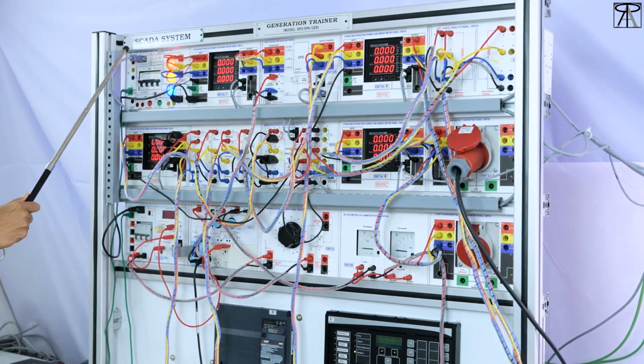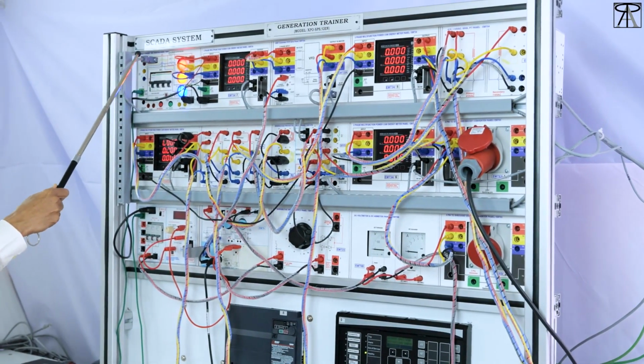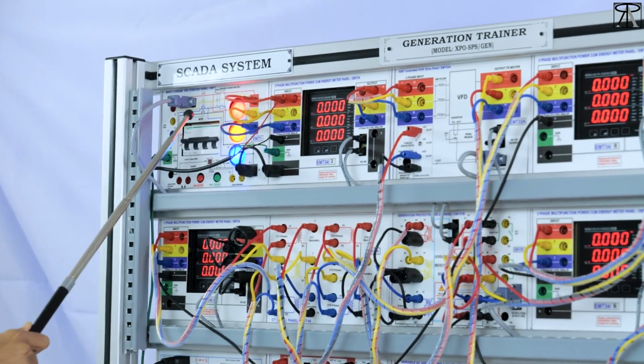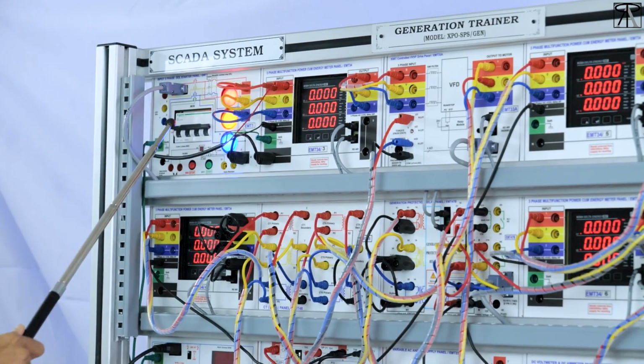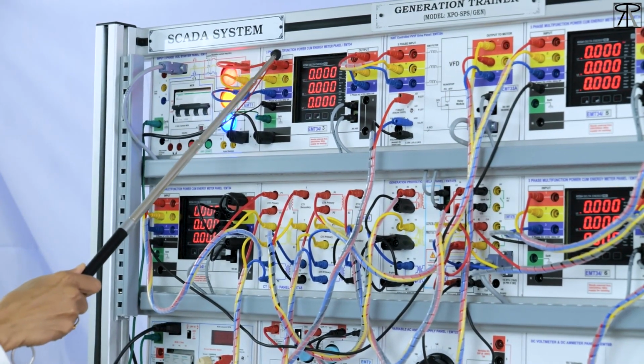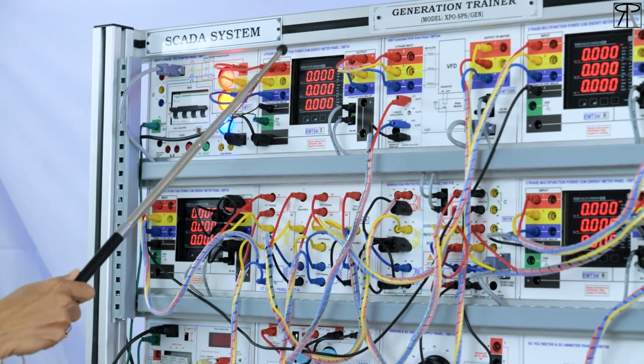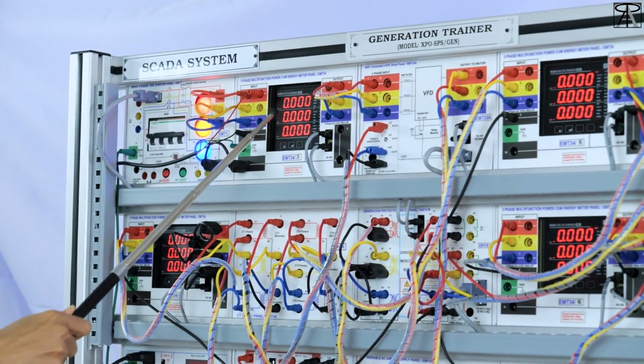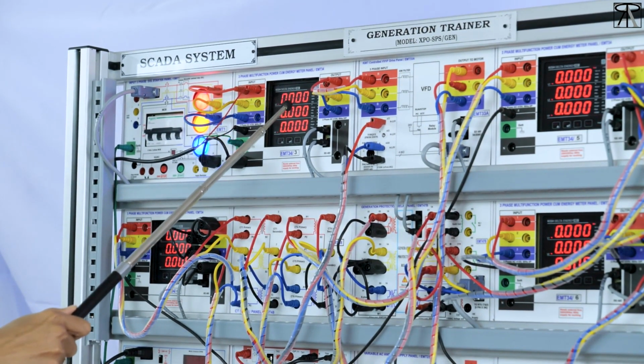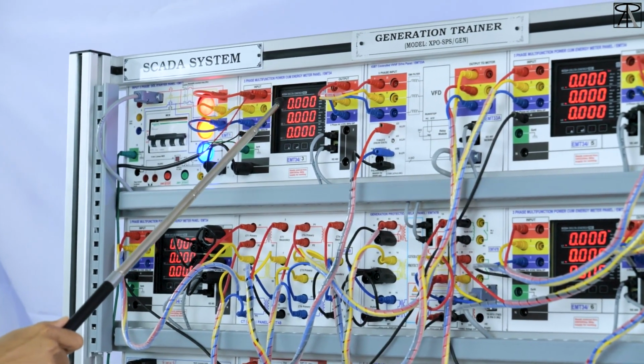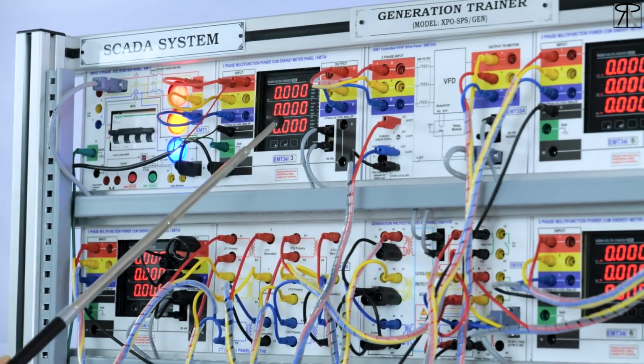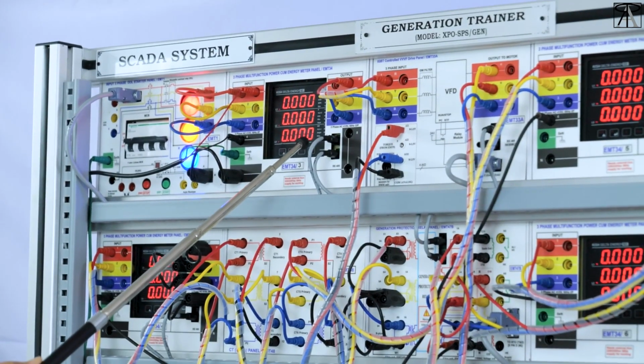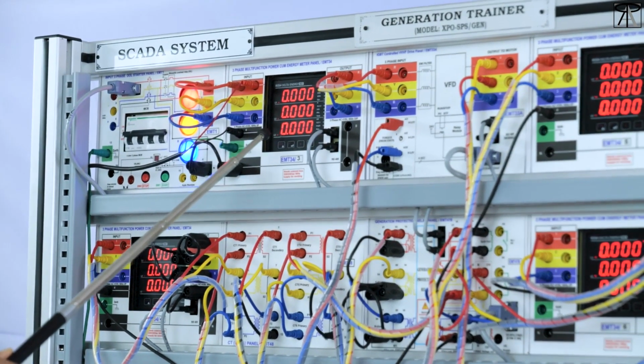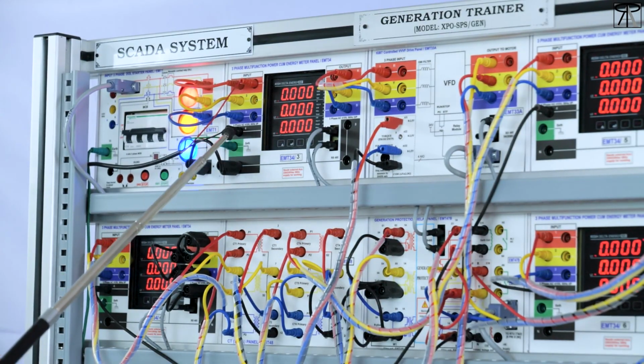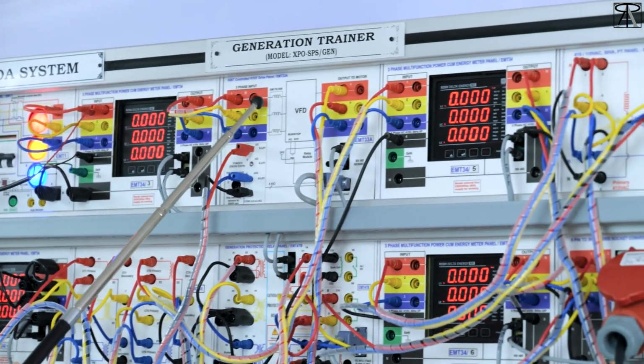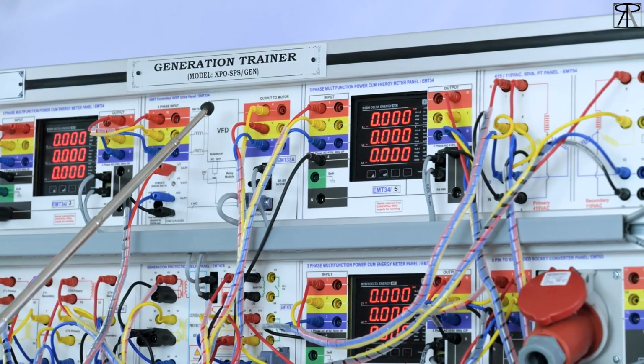And this is the starting point of the trainer, the 3-phase dual starter panel EMT1. It takes 440 volts from the power supply. This is the 3-phase multi-function power cum energy meter panel EMT34. It measures voltage, current, power factor, kW, kWh, more than 15 to 20 parameters. Both 3-phase and single phase can be measured, and with RS485 MODBUS, you can monitor these parameters on a PC as well as SCADA.